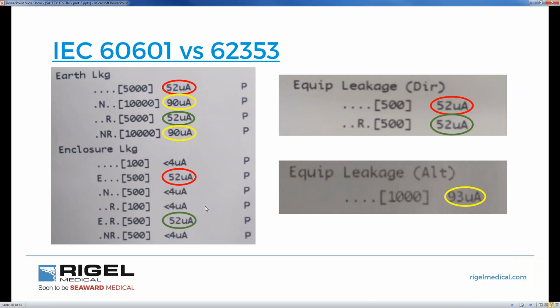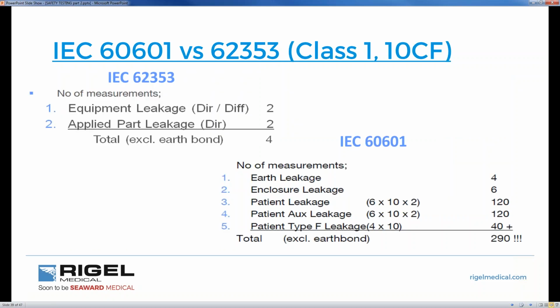So if I was to test the same medical device, what would my results look like? Well, this is our 60601 results here on a device, and this is our 62353 results on a device. There's our earth leakage, there's our direct leakage, same result. There's our reversed earth leakage, there's our reversed direct leakage. There's our neutral open, both reversed and in a normal condition, and this is our equipment leakage alternative. So that's how we can draw the conclusion, both with earth leakage and enclosure leakage, the direct comparison between 60601 and 62353. The big selling point really is time.